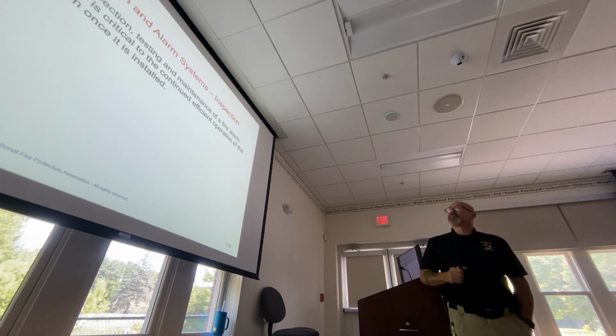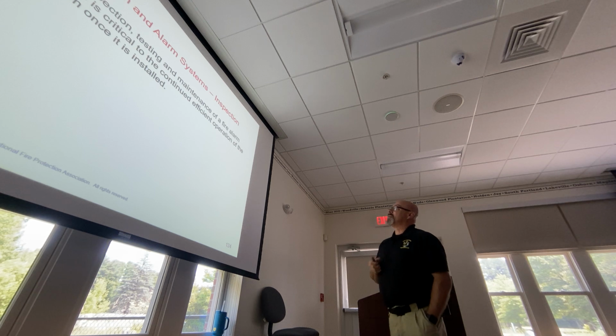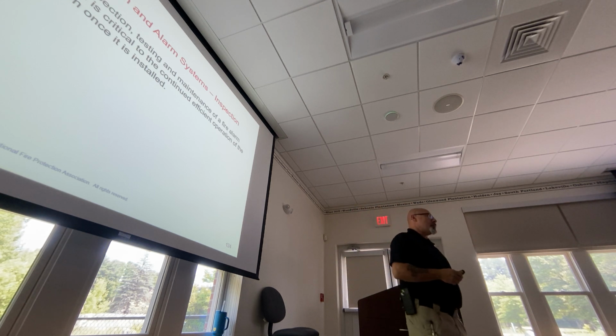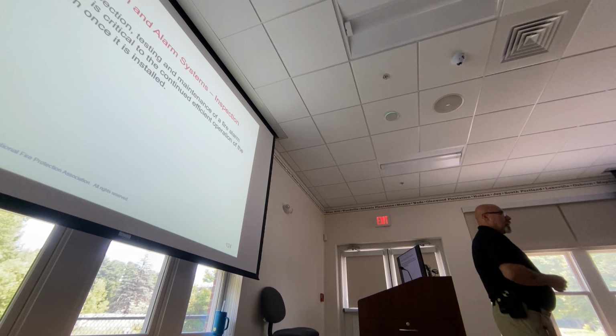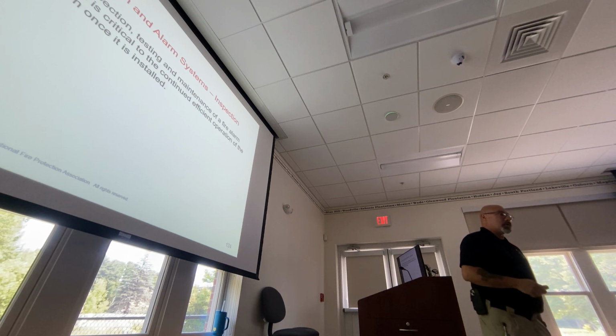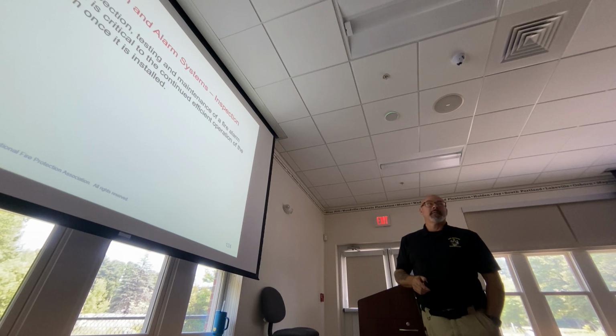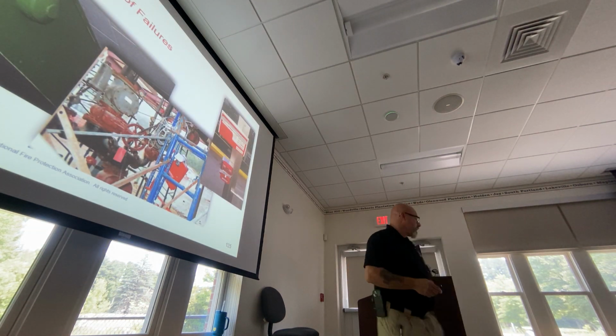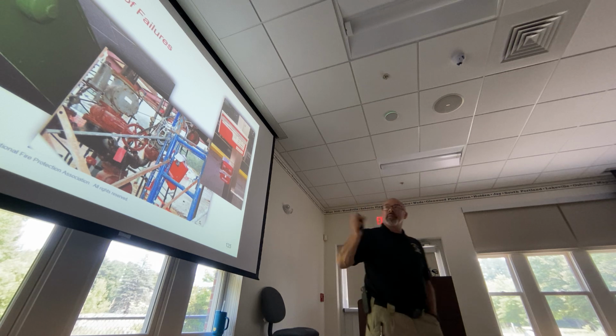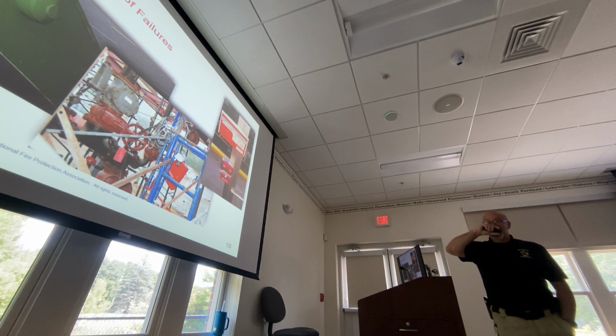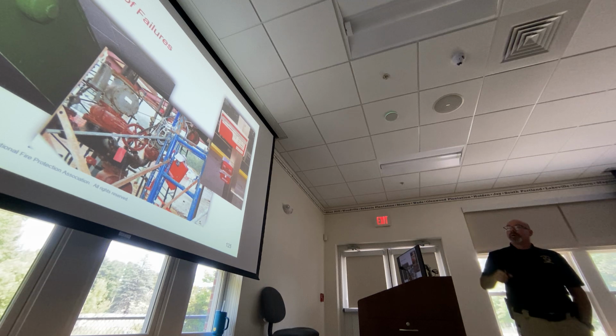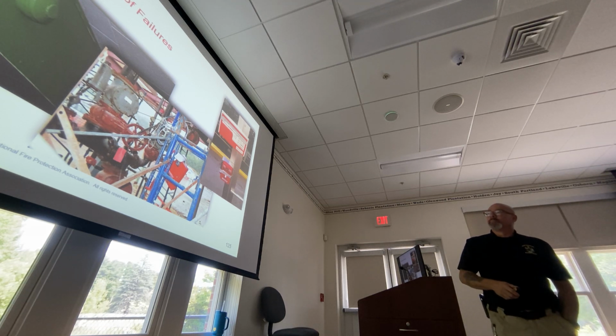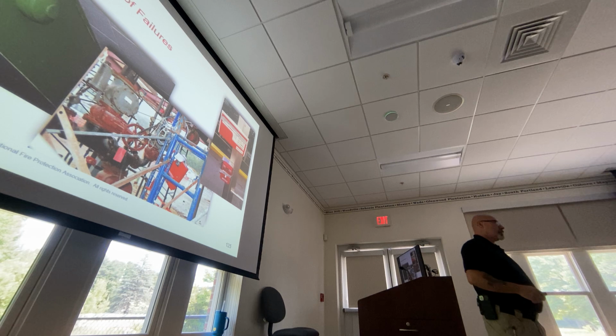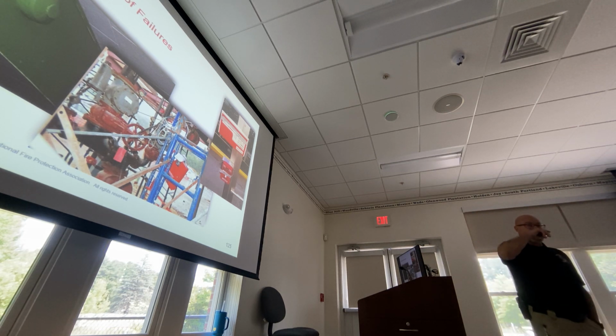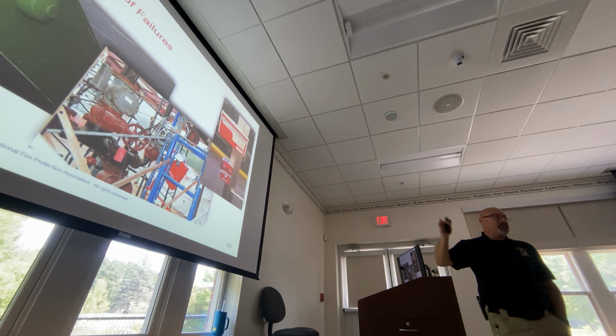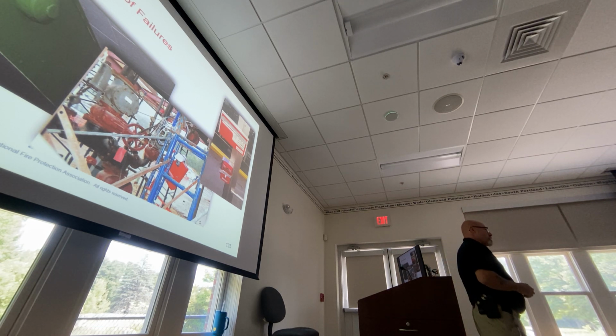So obviously the detection, inspections, testing and maintenance of a fire alarm system is critical to the operation, to ensure that it's going to run and continue to work over the lifespan of the system. All right, kind of like sprinklers, we have causes of failures. Here are some examples. What do we see here, and what things cause failures in a fire alarm system? Throw them out there.